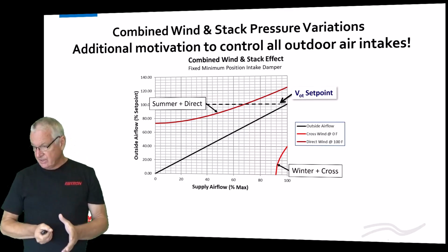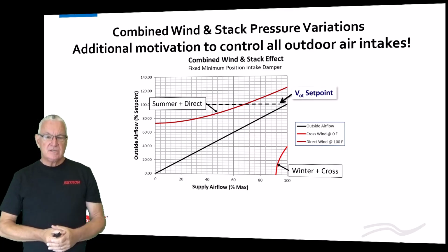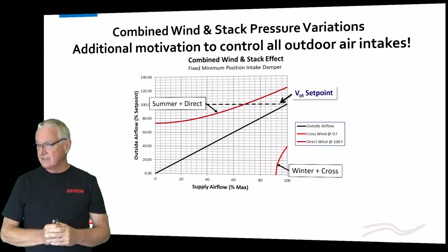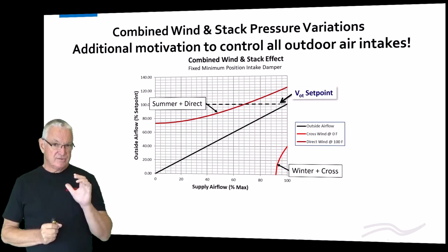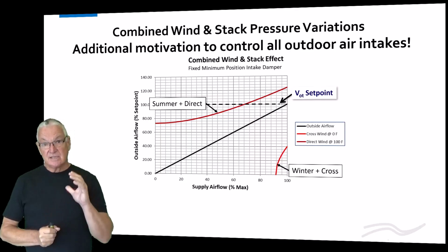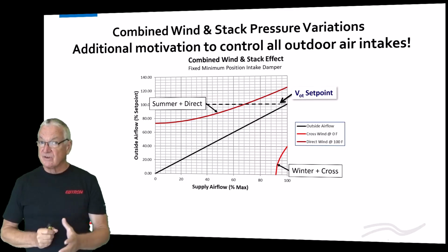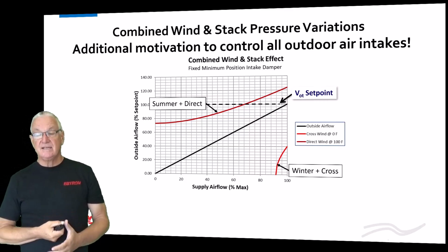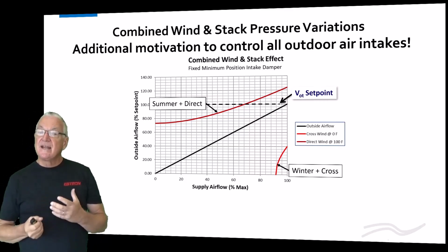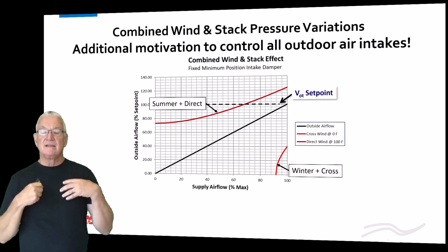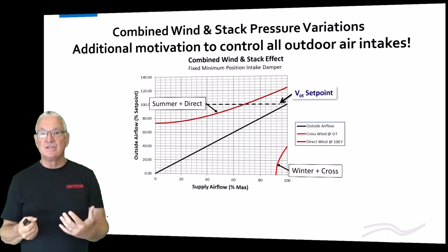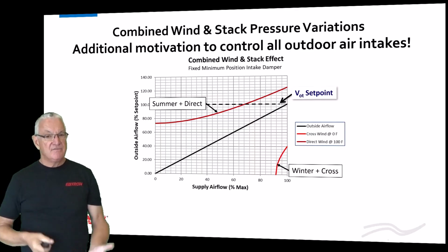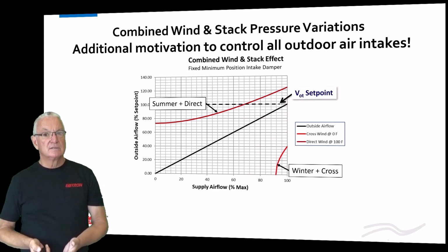And, honestly, we do this. I do this for balancers a lot because I want balancers to understand. Balancers do understand it, actually. But I've been doing this with balancers for years and years and years, and it's like, you go out and you set up a system and somebody comes out and checks your work and it's very different. Is it because you didn't do a good job, or is it because something else changed? And in a lot of cases, it's something else changed. And you just cannot go, static measurements in one instance in time does not do the job, okay? You have to control this out, and you can control this out. If you're measuring this, you control it out, all right?